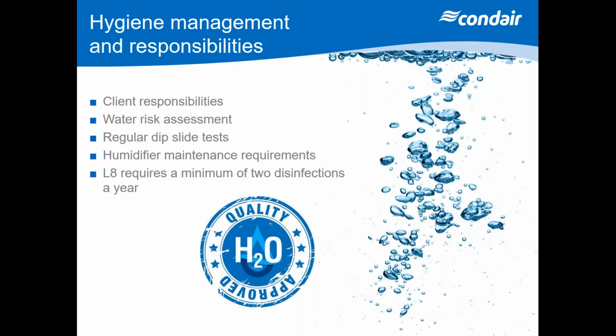Now, it's very, very important to make sure where you're taking these tests as well, because I've seen people taking tests back at their water storage tank, which is miles away from where the humidifiers are. So it's very important to make the tests in the inlet to the humidifier and also from the humidifier itself on a regular basis. Now, that can be either a weekly or a monthly thing, depending on what comes back on your water risk assessment. But as a minimum requirement for disinfection, it's normally 2 disinfections a year. And then you would change your disinfection regime depending on what your dip slides are coming back with. So it's always worth having that water regime in place as a backup to your system in terms of your standard 2 disinfections a year.